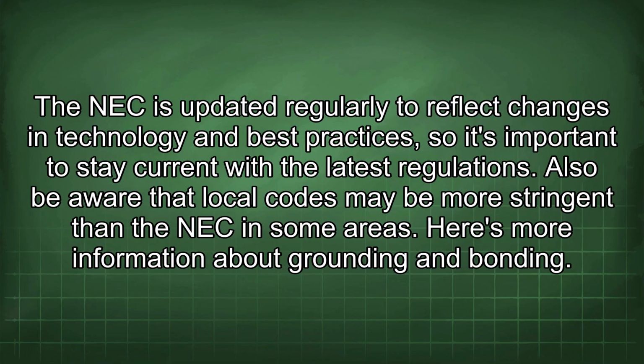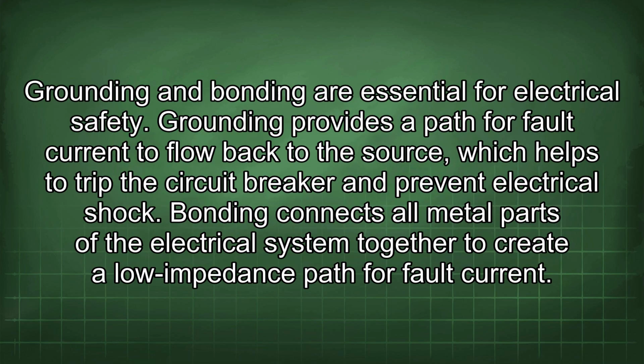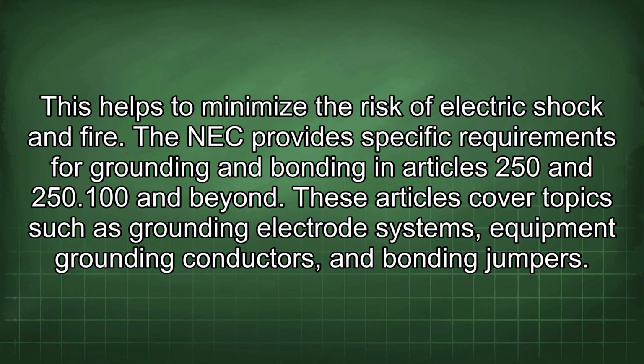Here's more information about grounding and bonding. Grounding and bonding are essential for electrical safety. Grounding provides a path for fault current to flow back to the source, which helps to trip the circuit breaker and prevent electrical shock. Bonding connects all metal parts of the electrical system together to create a low impedance path for fault current. This helps to minimize the risk of electric shock and fire.